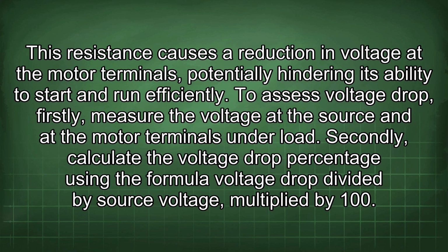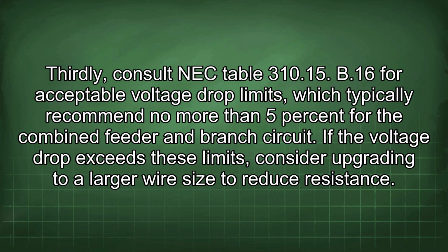To assess voltage drop, firstly, measure the voltage at the source and at the motor terminals under load. Secondly, calculate the voltage drop percentage using the formula voltage drop divided by source voltage, multiplied by 100. Thirdly, consult NEC table 310.15(B)(16) for acceptable voltage drop limits, which typically recommend no more than 5% for the combined feeder and branch circuit. If the voltage drop exceeds these limits, consider upgrading to a larger wire size to reduce resistance.